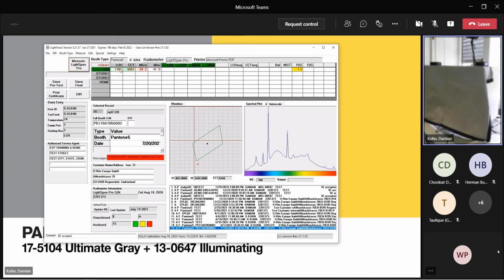The reading we see here is really an average of 10 readings, per the setting we have here. What we do is take 2 readings, so 2 times an average of 10, and that gives us 2 times a reading. So we have lux and CCT. MI visible and MI UV are recorded here, but not really stated on the certificate. We will probably do this at a later stage, but we are not yet ready to document these for customers. That's helping us now to collect data and come up with some test limits for those later on.